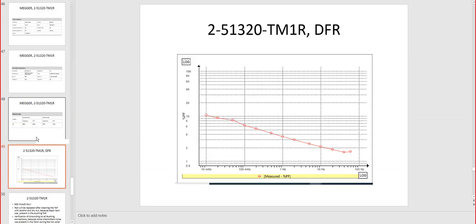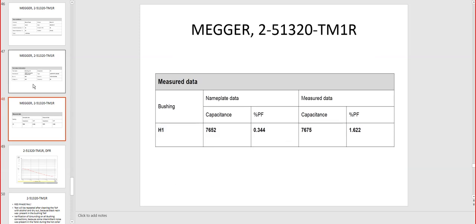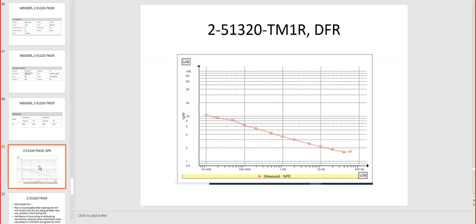and then the next one will be the power factor, nameplate data and measured data, which you can see the problem here. The power factor is actually a few times higher, so the manufacturer data is asking for a power factor 0.344. We found the power factor is 1.6. So we're going to see that was a bad reading, and it wasn't actually a real bushing defect. But at the moment when the reading was done, we were unsure what actually happened, so we could not energize the transformer. So that's the bottom line.